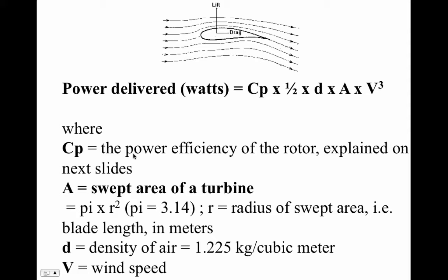The area of the wind turbine is related to its radius squared, so it's not directly related to how big it is linearly — it's related to area squared. What's really important is the area swept by the wind turbine — that's the collection area, the path laid out by the rotation of those blades. It's related to the blade diameter squared. So every time you double the radius or diameter of a wind turbine, you get four times the power output. You go from a 10-foot diameter wind turbine to a 20-foot diameter wind turbine and you get four times — not twice — the power.